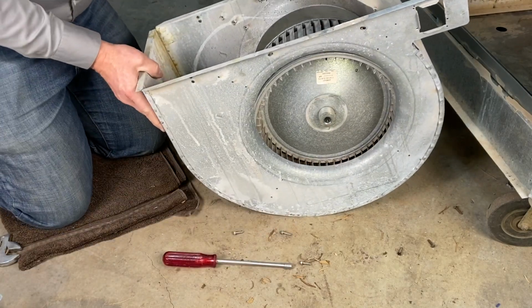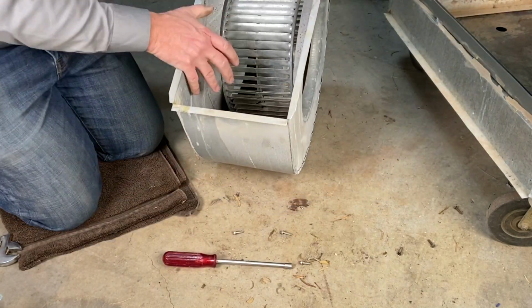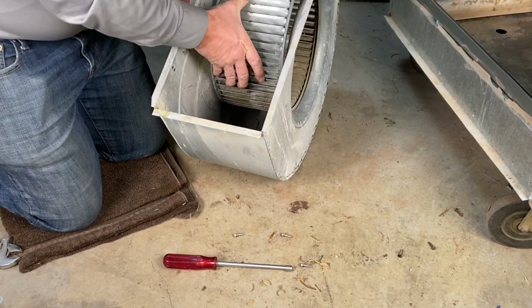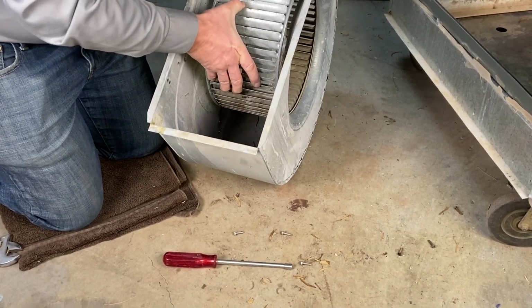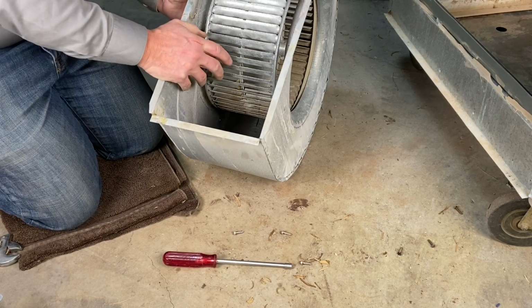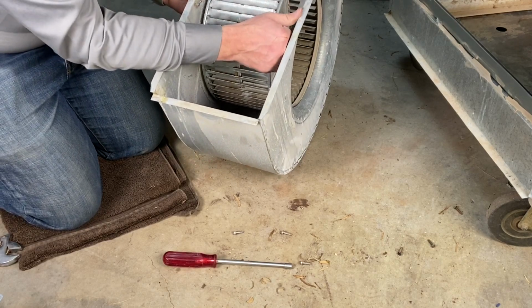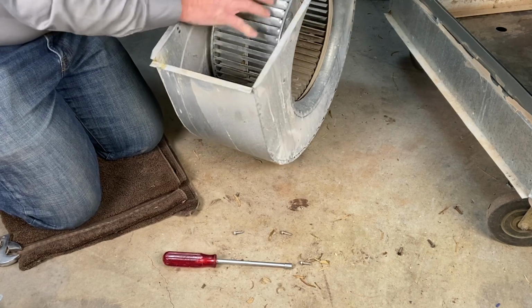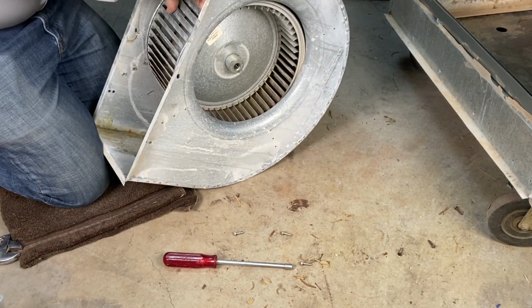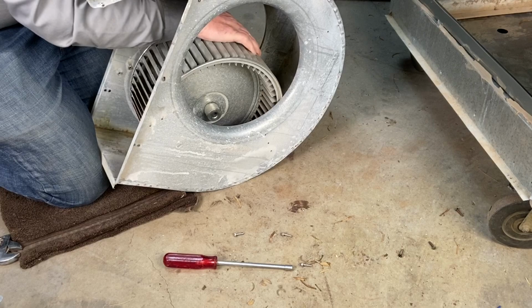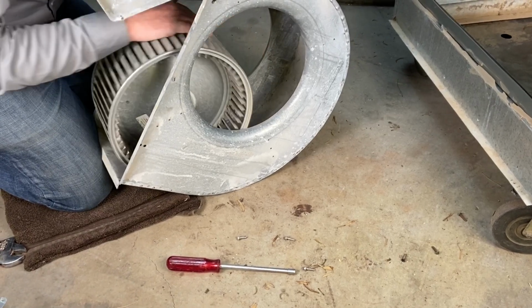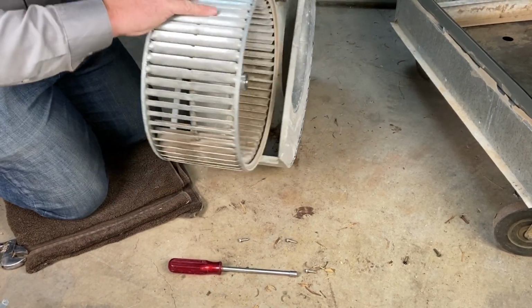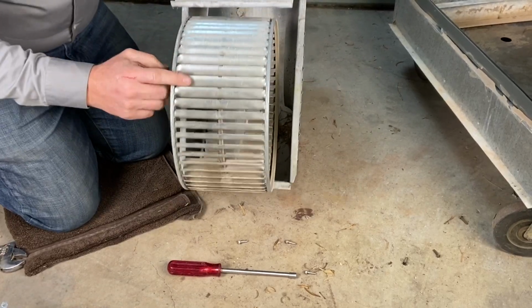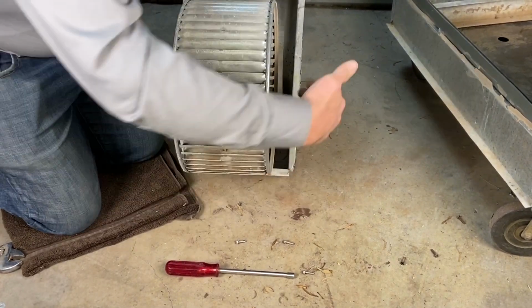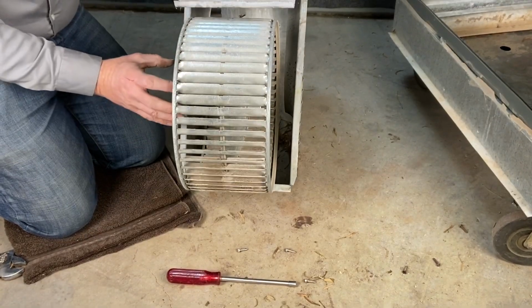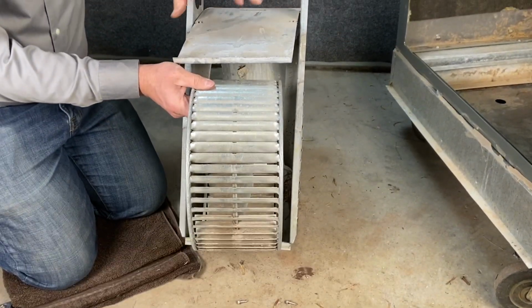Now when I'm washing the blower, I like to always wash it in the housing. But if we need to replace the blower wheel, we'll need to pull it out of the housing. And this particular brand makes it very tight, so it's going to be a little bit of a pain to pull it out, but it's all right. Now as I'm pulling it out, notice which way the fins go. I have my hub on this side and my motor mounts on this side. It's very important we put it back in that same direction.